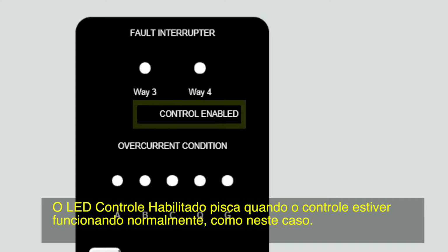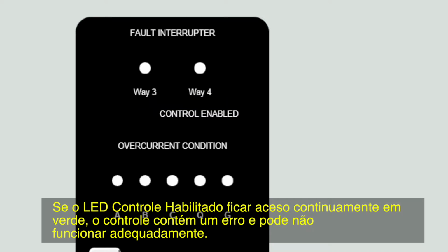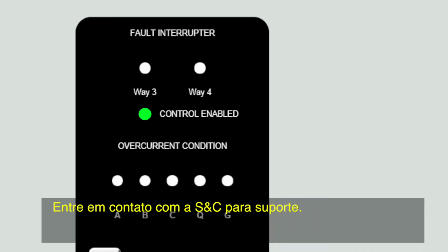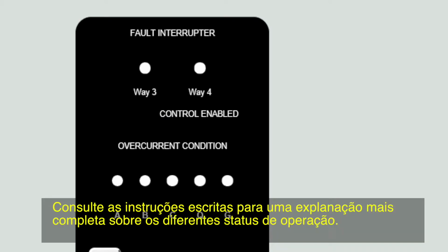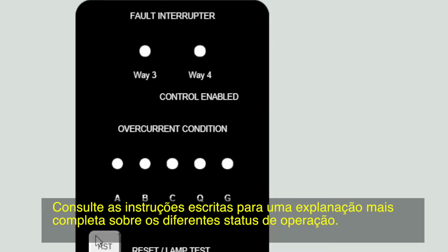The Control-enabled LED will blink when the control is working normally, as it is now. If the Control-enabled LED is solid green, the control has an error and may not perform properly. Contact S&C for support. See the written instructions for a more complete explanation of the different statuses.